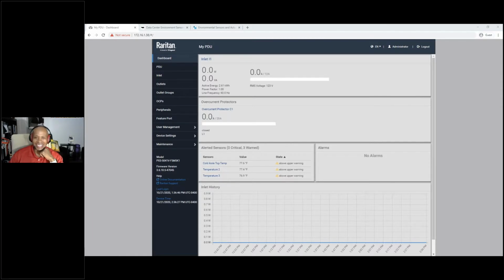One thing I did want to mention, in regards to the placement question we got during Bruce's time: what we see a lot of customers doing is follow the ASHRAE guidelines for the cold aisle, doing a top, middle, bottom placement, and then for the hot aisle they'll place a single sensor and measure the differential between the cold aisle and hot aisle. That seems pretty common, but the ASHRAE guidelines document that Bruce shared will show they recommend 3 sensors per side — they explain that a lot better in the document.